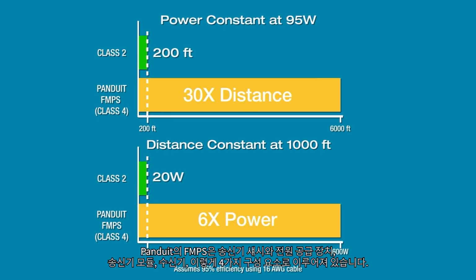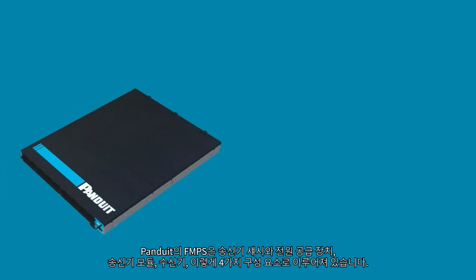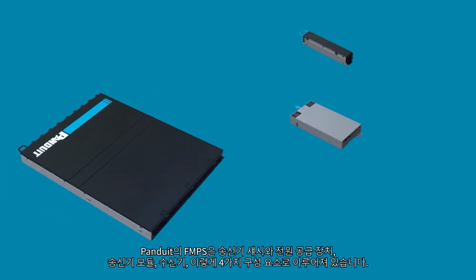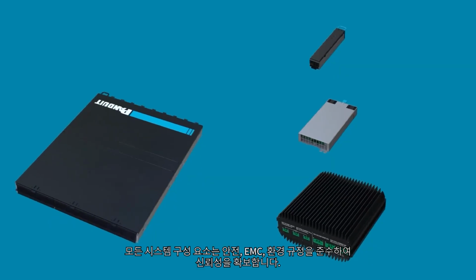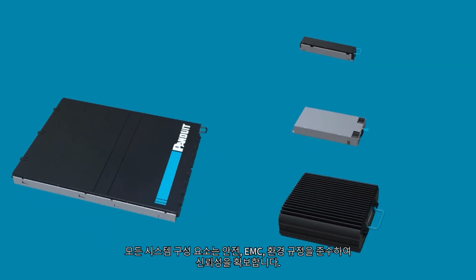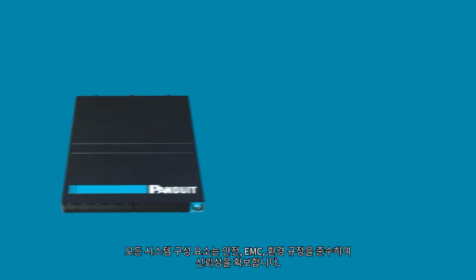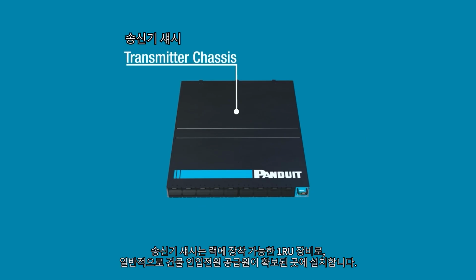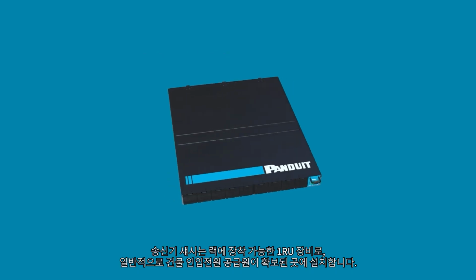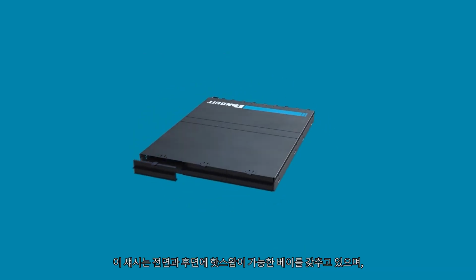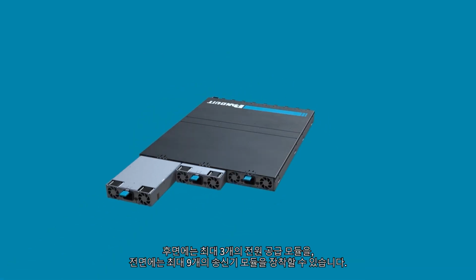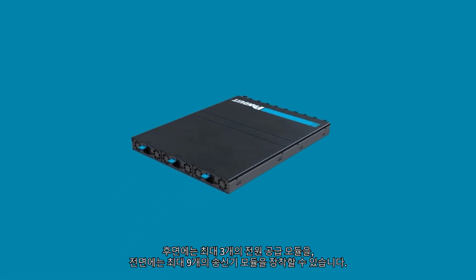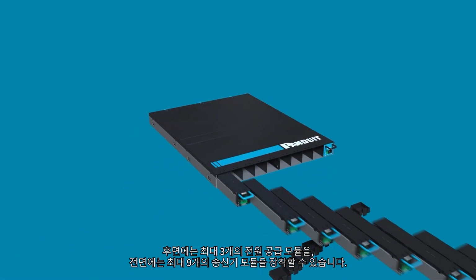The Panduit Fault Managed Power System consists of 4 components: transmitter chassis, power supply unit, transmitter module, and receiver. All system components comply with safety, EMC, and environmental regulations for reliability. The transmitter chassis is a rack-mountable 1RU chassis that usually resides at the head end of a building where a local power source is available. The chassis has hot swappable bays in the front and back. It can take up to 3 power supply modules in the back and up to 9 transmitter modules in the front.